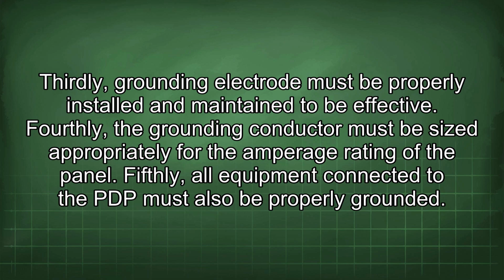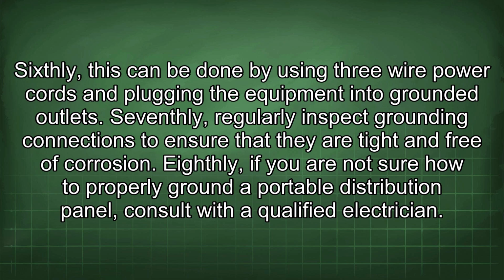Fourthly, the grounding conductor must be sized appropriately for the amperage rating of the panel. Fifthly, all equipment connected to the PDP must also be properly grounded. Sixthly, this can be done by using 3-wire power cords and plugging the equipment into grounded outlets. Seventhly, regularly inspect grounding connections to ensure that they are tight and free of corrosion. Eighthly, if you are not sure how to properly ground a portable distribution panel, consult with a qualified electrician.